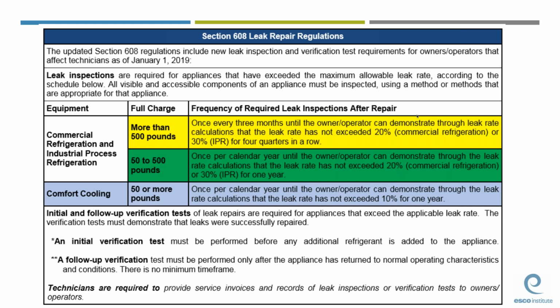The guidelines for commercial refrigeration and industrial process refrigeration systems are broken down into two ranges. Those are shown by the yellow and the green sections on the chart, and these are based on the total refrigerant charge. One section is from 50 to 500 pounds of charge, and the other range addresses systems that contain more than 500 pounds of refrigerant. For commercial refrigeration and IPR systems that contain between 50 and 500 pounds of refrigerant, a follow-up leak inspection must be conducted once per calendar year to show that the system no longer violates the leak rate limit. For commercial refrigeration and IPR systems that contain more than 500 pounds of refrigerant, follow-up leak inspections must be conducted every 3 months, once a quarter, for 1 year, to show that the system no longer violates the leak rate limit. This is an extremely important chart that contains a great deal of new information that your students must be aware of.